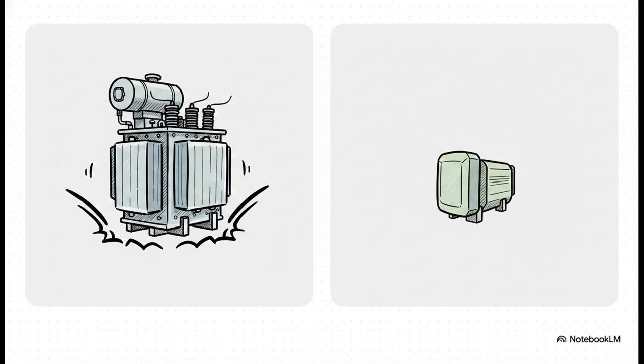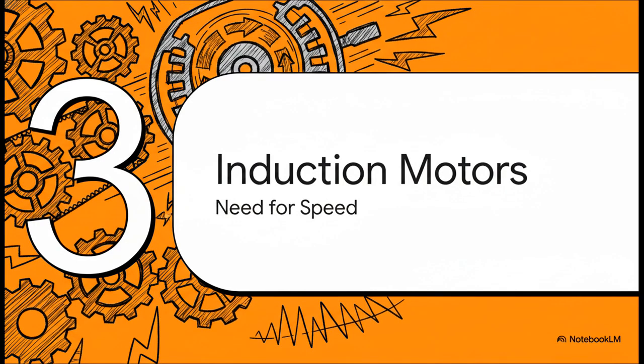And this leads us to our very first real-world physical consequence. Because a 60 hertz system needs less magnetic flux, the physical iron core of the transformer doesn't need to be nearly as big. They can be manufactured to be smaller, lighter, and way more cost-effective. But on the flip side, a 50 hertz transformer needs a lot more iron and copper to prevent magnetic saturation, making it noticeably bulkier and a whole lot heavier. All right, section 3, need for speed induction motors.